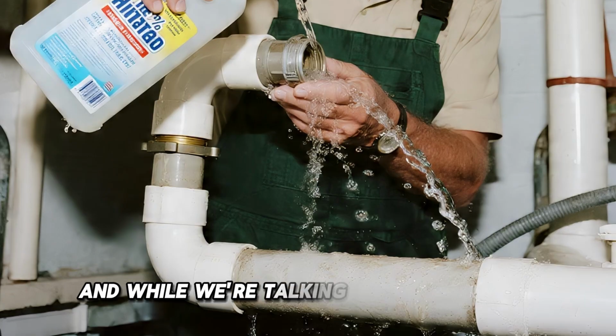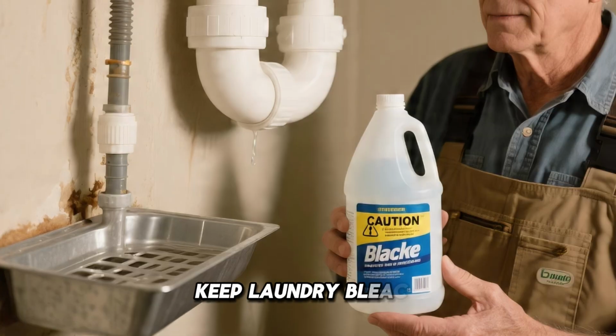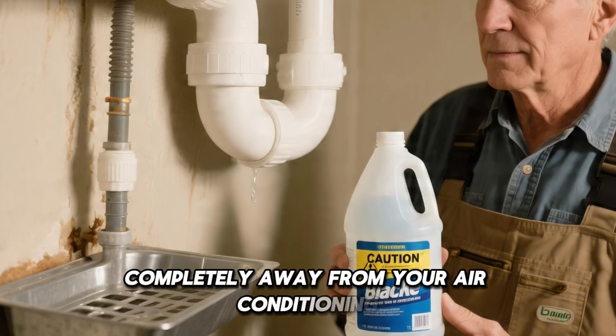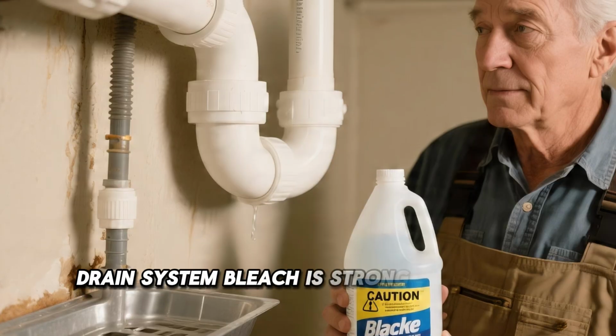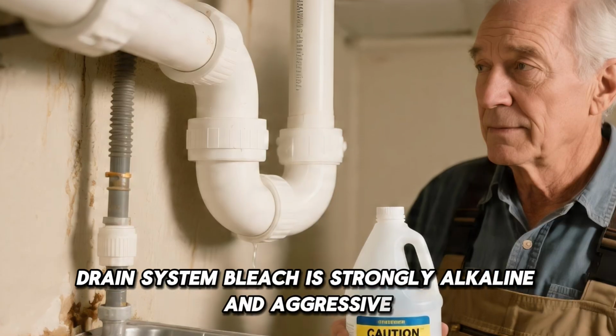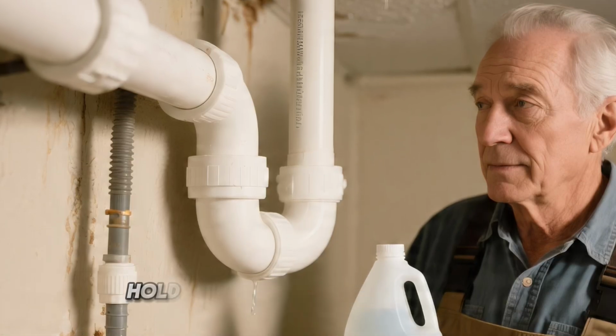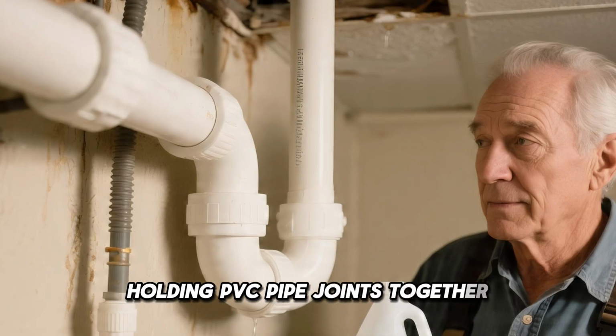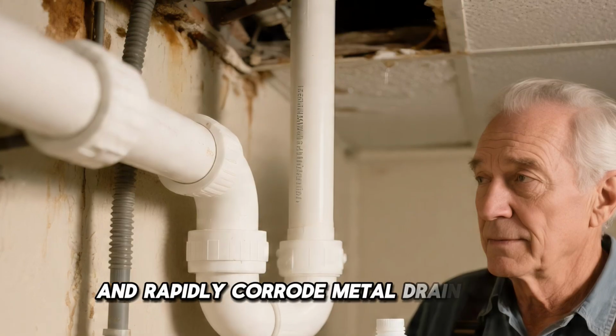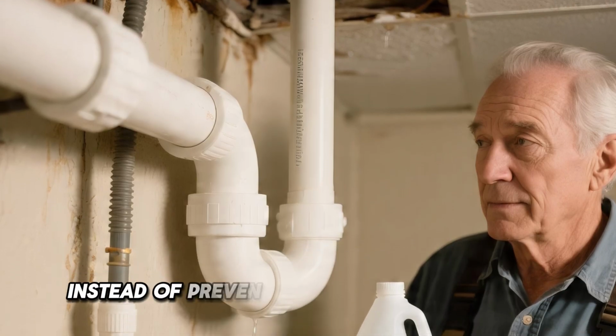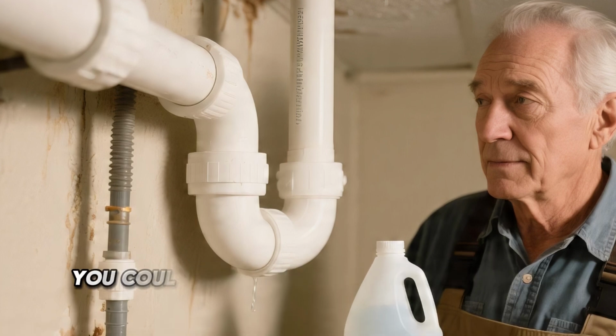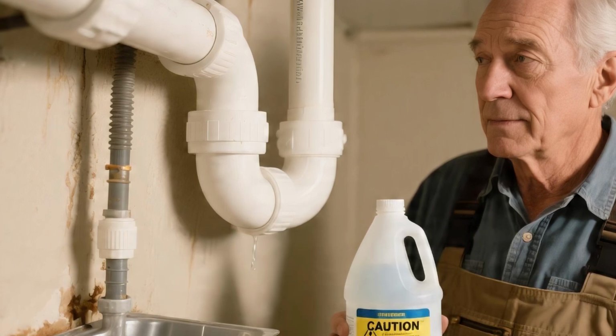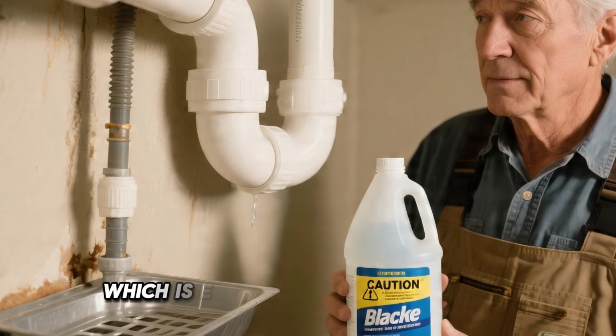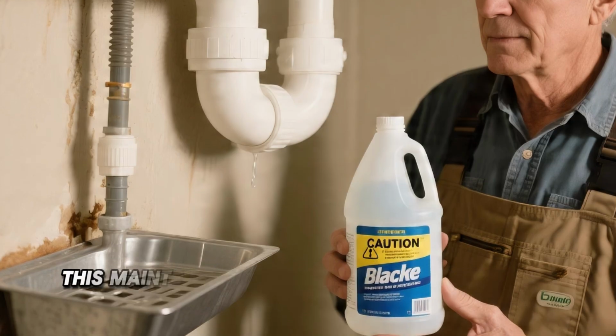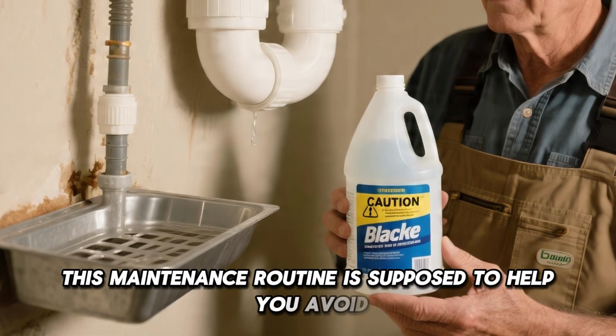And while we're talking about chemicals, keep laundry bleach completely away from your air conditioning drain system. Bleach is strongly alkaline and aggressive. It can degrade the cement holding PVC pipe joints together and rapidly corrode metal drain pans. Instead of preventing an expensive problem, you could end up creating a major water leak behind the drywall, which is exactly the kind of disaster this maintenance routine is supposed to help you avoid.